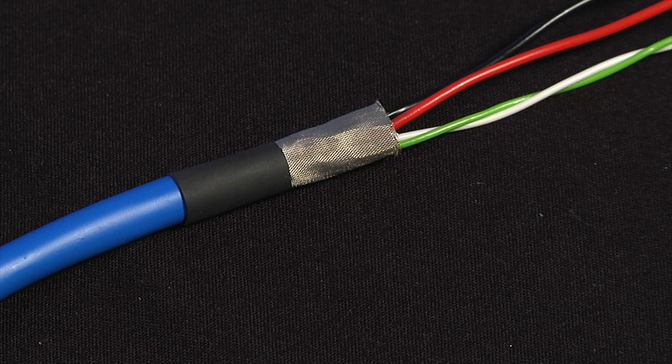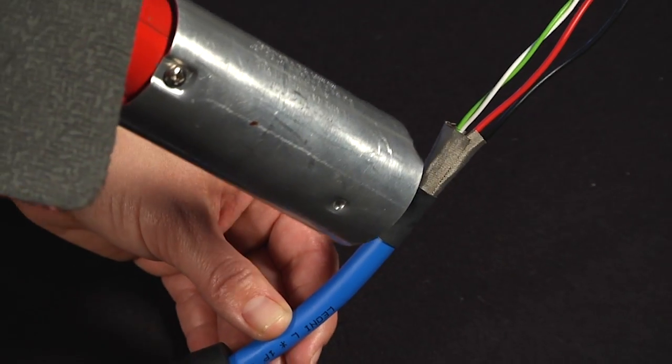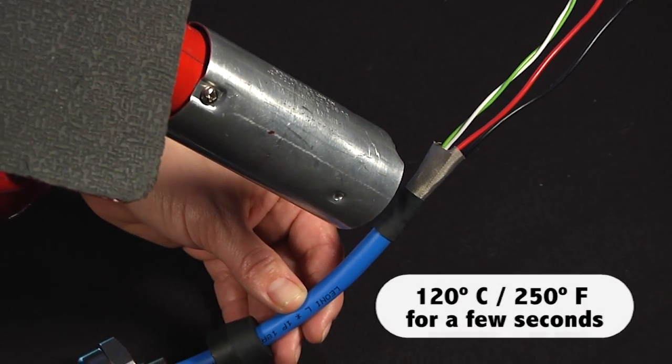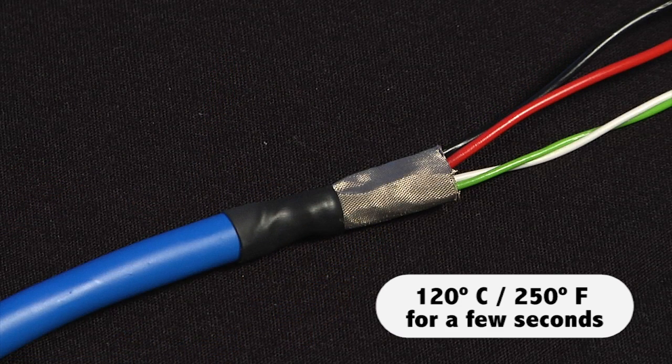To attach the heat shrink to the cable, slide the shielded heat shrink over the cable until the tubing completely covers the foil shield and the drain wires. If it doesn't completely cover the foil and drain wires, trim the foil back until it does. Carefully apply heat to shrink the tubing. 120 degrees Celsius or 250 degrees Fahrenheit for a few seconds should do it.